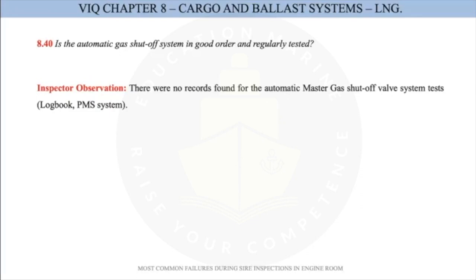So the shutoff system, the automatic shutoff valves, are valves which are closing, like branch valves, and they cut off the complete gas supply to a particular consumer, to the engine, to the GCU or boiler or whatever. Usually they trip in case of gas detection or some other scenario, and they should be tested. And these tests should be recorded in the logbook or planned maintenance system. The Coast Guard in the USA likes to check this usually. Not usually, always. And a real test.